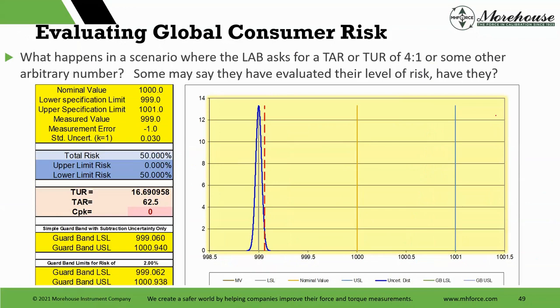And then what happens when a lab asks for a TAR or TUR 4-to-1 or some other arbitrary number? It's what happens. Some say, okay, if I send this to X lab and I know my TUR is greater than 4-to-1, we're good. And here's that example I was talking about. When it's on the specification limit, our measured value right here is right on the specification limit. TUR is 16.69. TAR is 62.5. CPK went to 0. And look at the risk, 50%, no matter what.